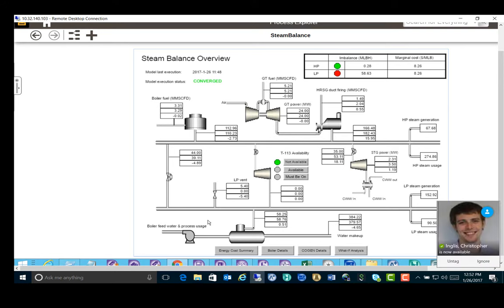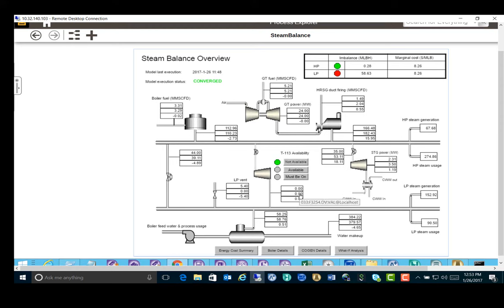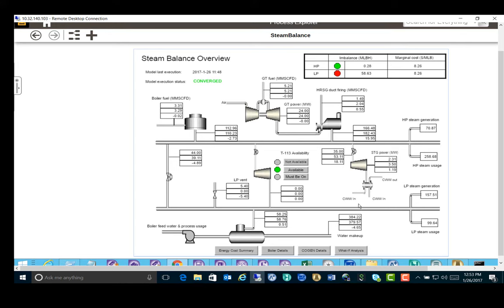In this particular demo, the boiler feed water pump could be driven either by the steam turbine T-113 or electric motors. In current conditions, it uses electric motors, therefore the steam flow from the turbines is zero. And because the equipment availability on the T-113 is set as not available, the optimized value also equals zero. If the user clicks on the available button, that will set the equipment availability to available. After five minutes until the next cycle is completed, we should come back to check if this optimum value has changed. For now, let's move on to the what-if analysis screen.